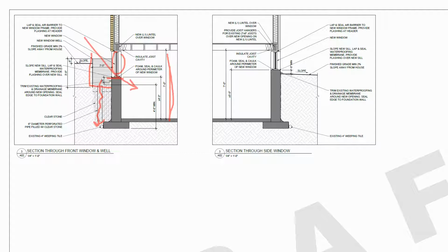And then this is that rear window on the side. So the problem here is, again, the property line is roughly there, and this space, we need another couple feet basically in order to allow just a traditional window by building code standards. So the shutter would be about there, and again, if that were activated due to fire, that would roll down and protect the neighbor's building from fire spreading out through that window. Or again, we could do a fire rated window, but that could be pretty costly again.